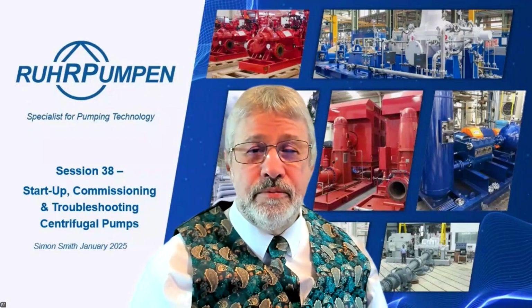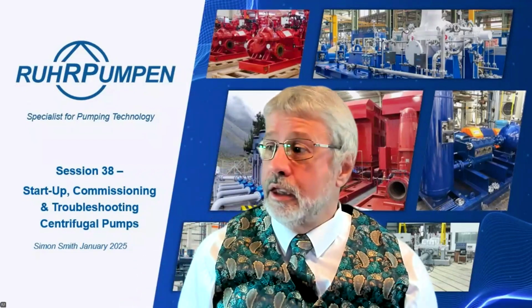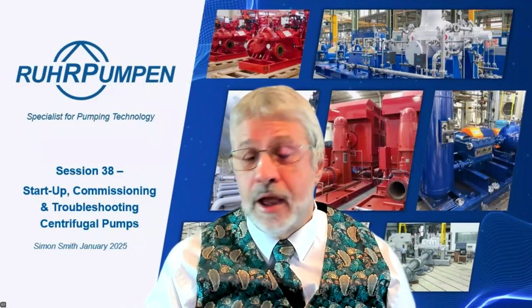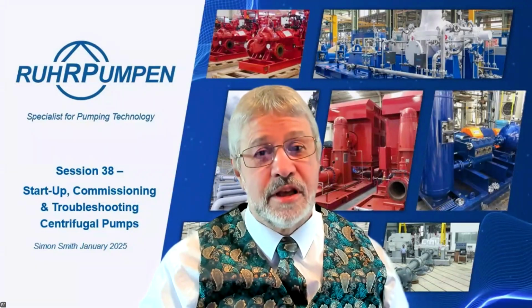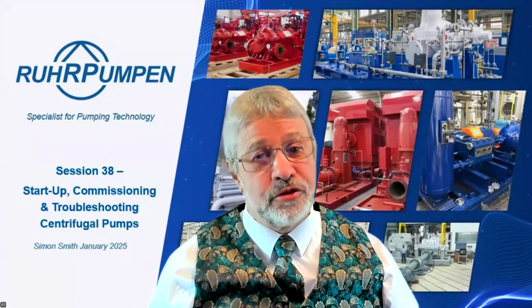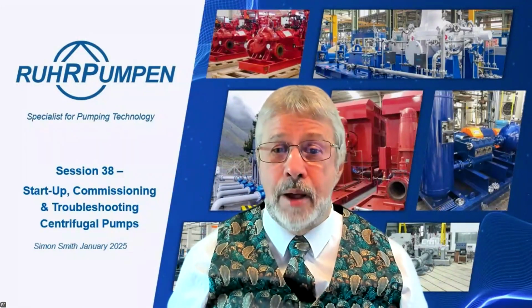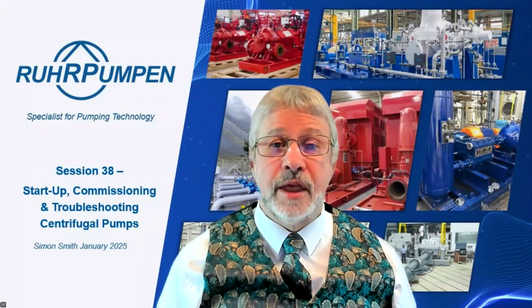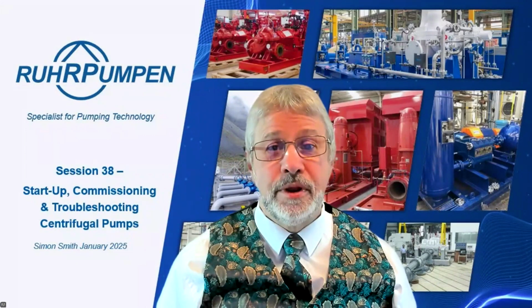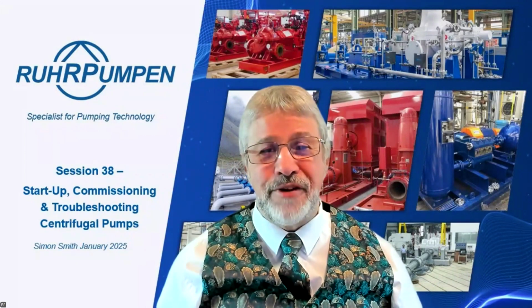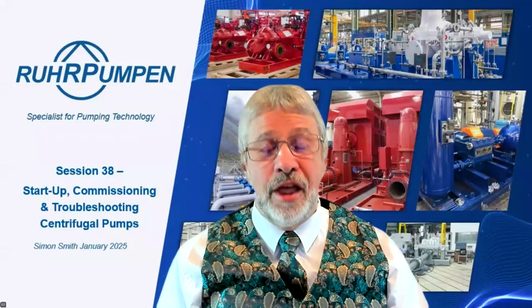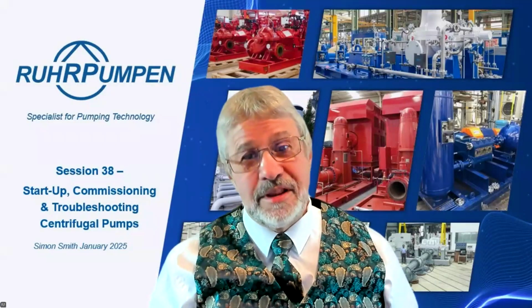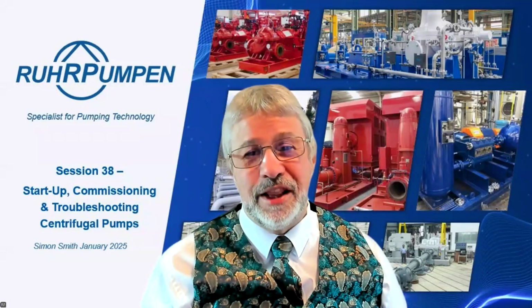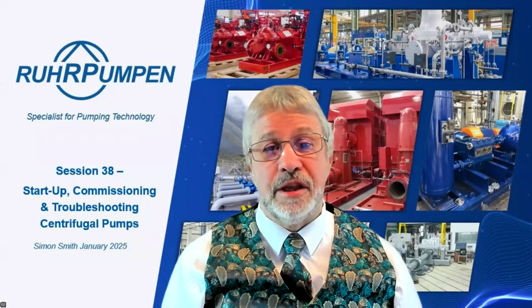Sometimes you'll get a pump natural resonant frequency problem, or a system natural resonant frequency problem. That's common because every installation is different and you sometimes can't predict that. And it can commonly be, especially on vertical pumps, VS6s, VS1s, they can get to site, and the pump, which was running absolutely fine in the factory, when you get it into site and get it into the pipework system, you hit a natural resonant frequency, and then you need to make some adjustments to the installation.